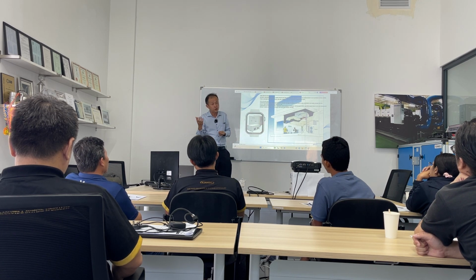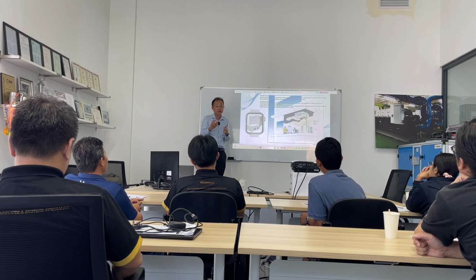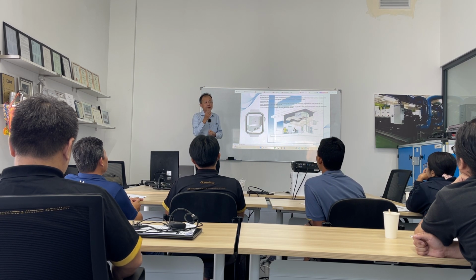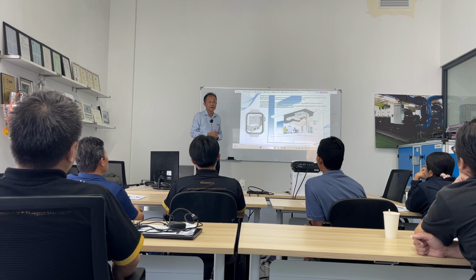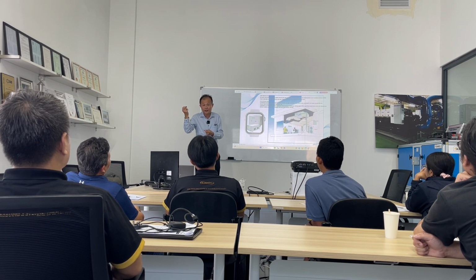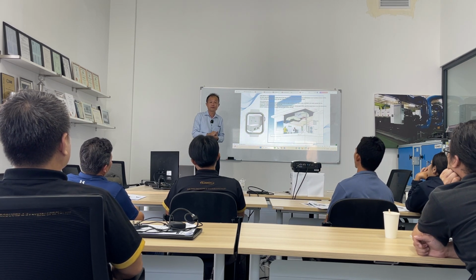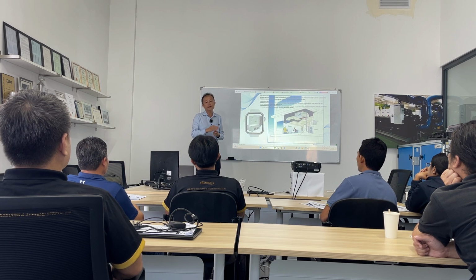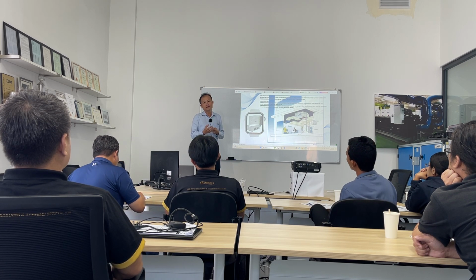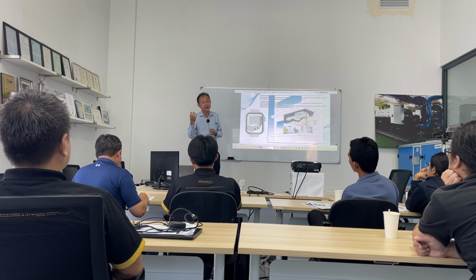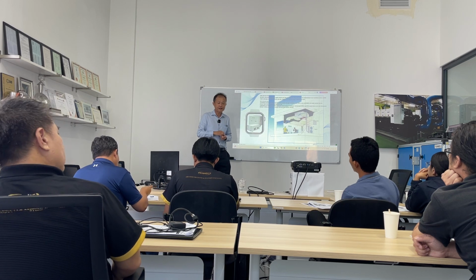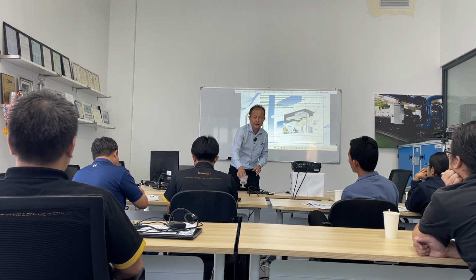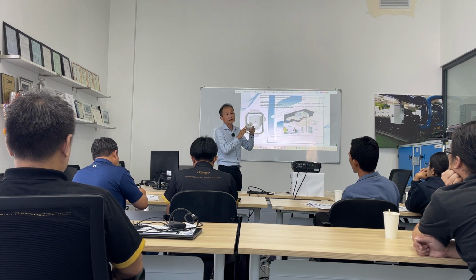But in order for them to come out into a physical, visible structure, you need to provide a surface lower than the temperature they need to condense. That means to convert from the moisture in the vapor form into the liquid. So dew point is a temperature where the moisture in the vapor form starts converting into liquid. So whenever you have a surface temperature lower than the dew point, the water drops from it.